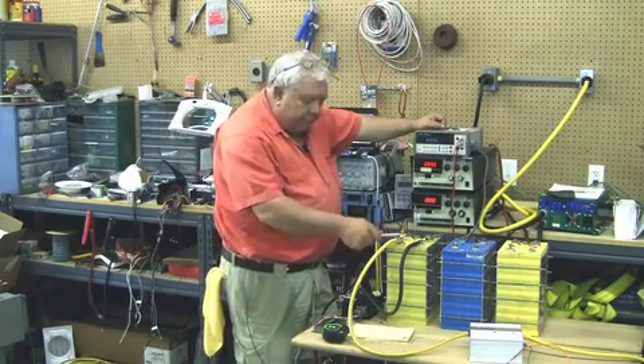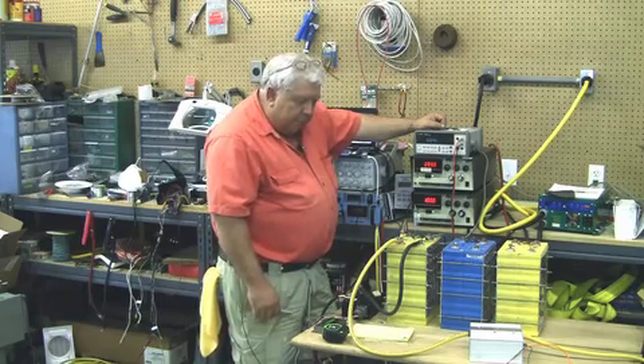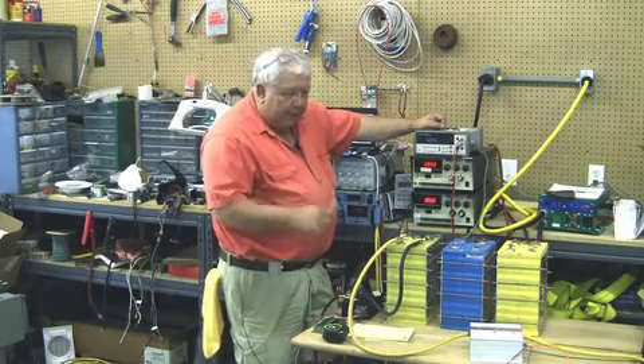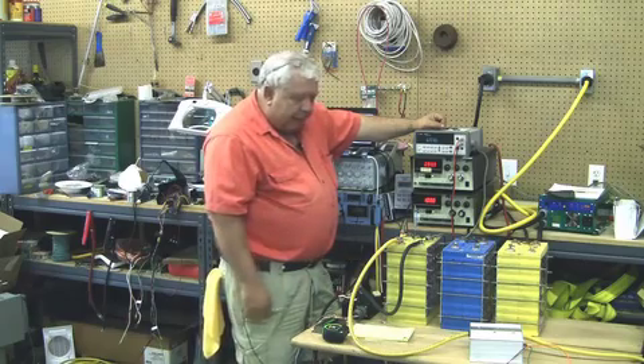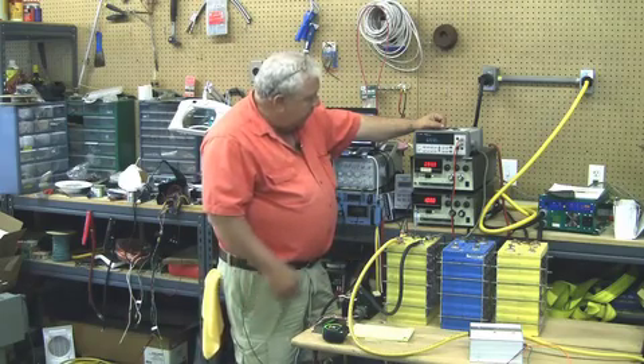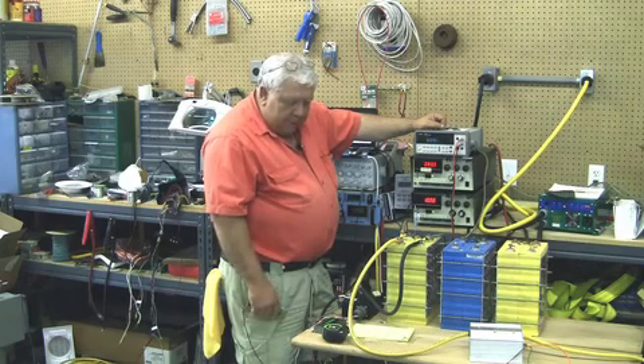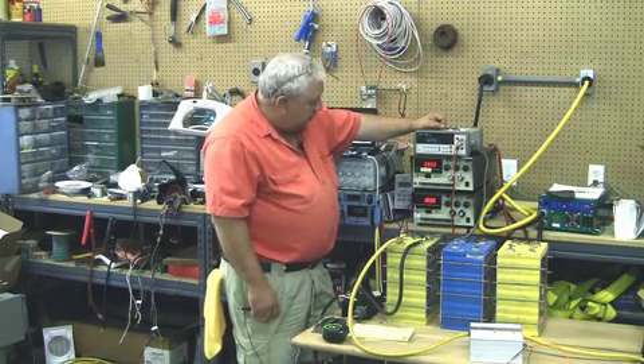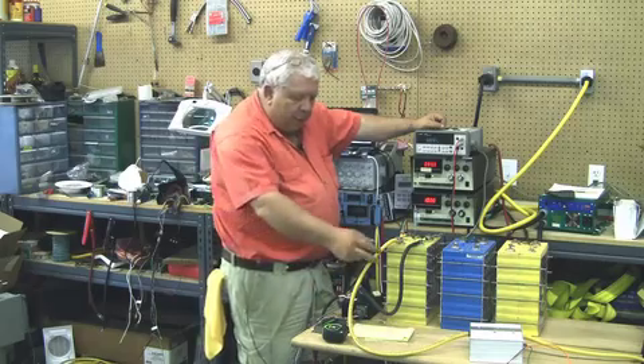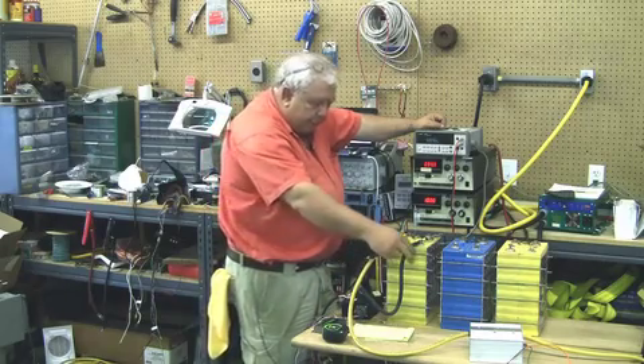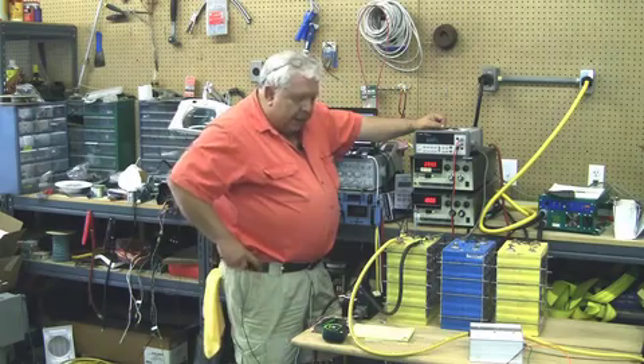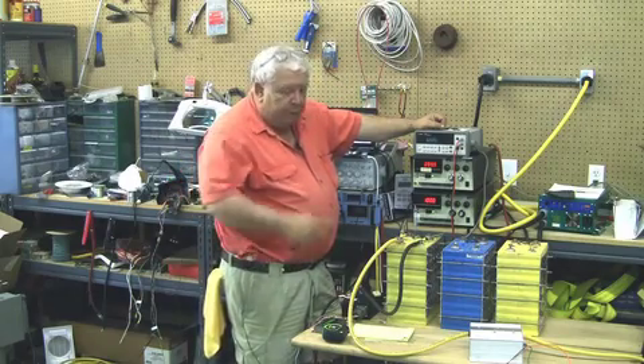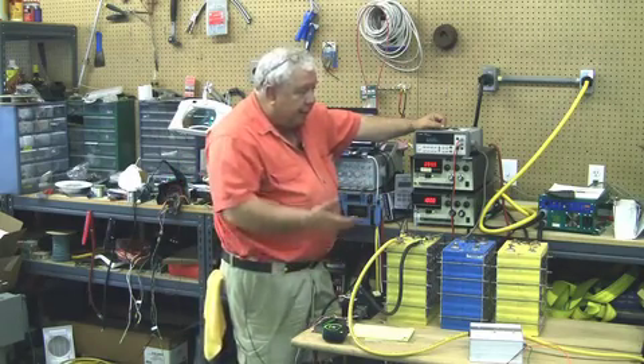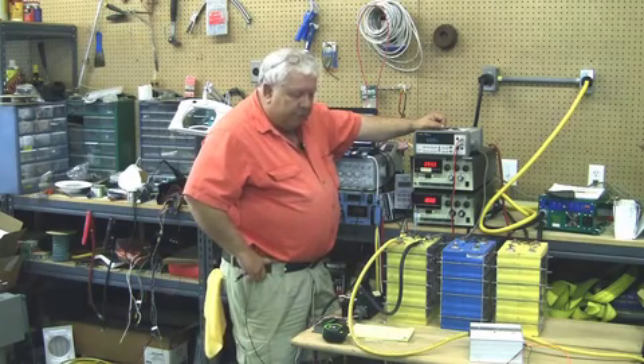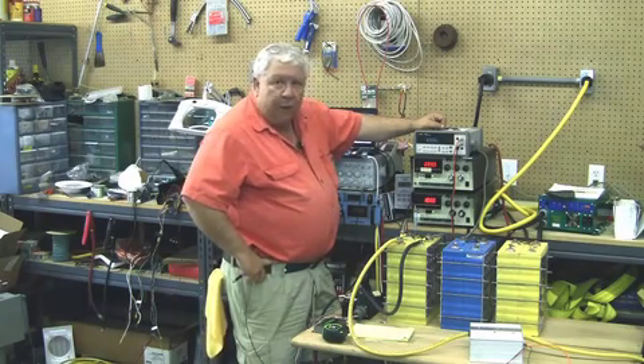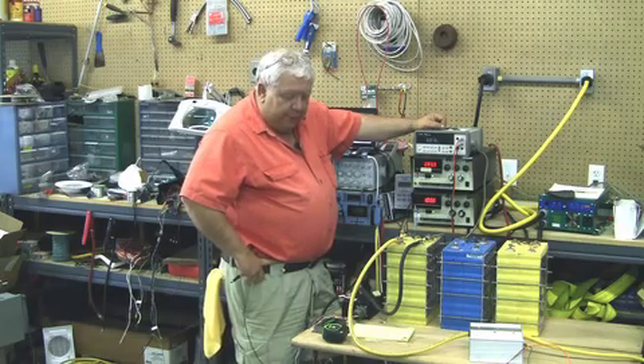You have to use cables with good connectors, bolted down, not alligator clips and so forth, because we're doing 200 amps out of this thing at 6 volts. That's 1,200 watts or so. Right now, but it's enough power that at these current levels, these cables will get warm, and I've actually melted some when I tried to do even the big clips, like a battery booster cable. They're not meant to sit there for 2 hours with 200 amps on them, even if they're rated for 200 amps.